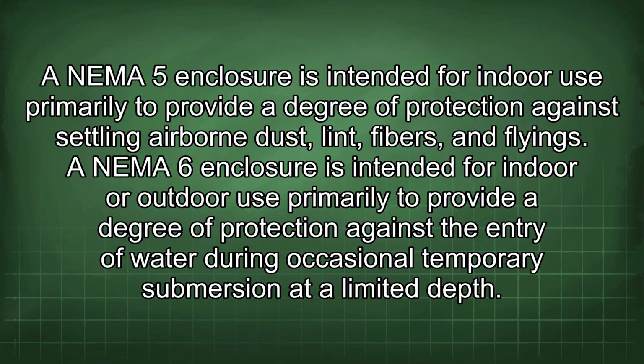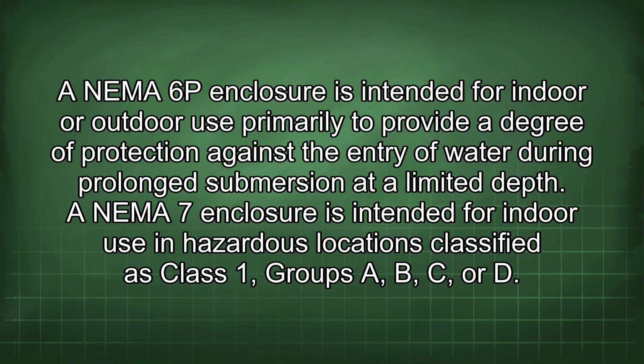A NEMA 5 enclosure is intended for indoor use primarily to provide a degree of protection against settling airborne dust, lint, fibers, and flyings. A NEMA 6 enclosure is intended for indoor or outdoor use primarily to provide a degree of protection against the entry of water during occasional temporary submersion at a limited depth. A NEMA 6P enclosure is intended for indoor or outdoor use primarily to provide a degree of protection against the entry of water during prolonged submersion at a limited depth.